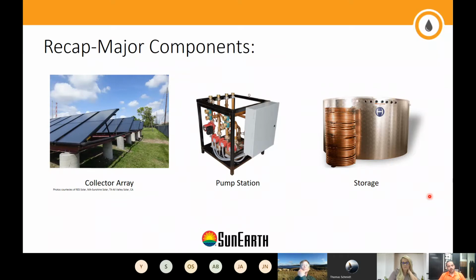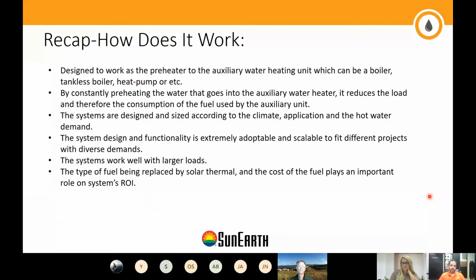How they work: solar thermal systems are always designed to work as a preheater to the auxiliary system. Whenever you're designing a solar thermal water heating system, you have to design an auxiliary system the normal way you would have designed it. Whatever heater you're putting in, whether gas, electric, or whatever your auxiliary or backup heater is, it has to be sized to meet the entire demand of the building, just as you would have done without the solar thermal.